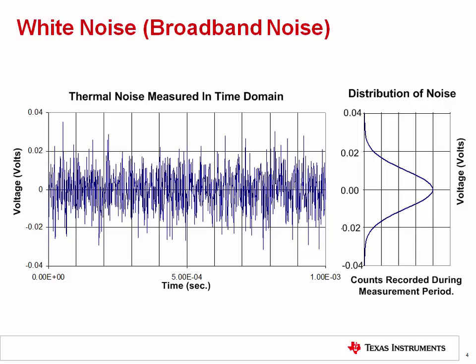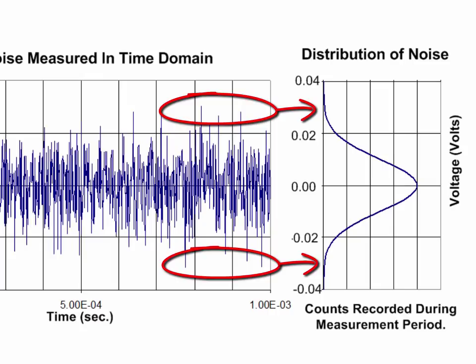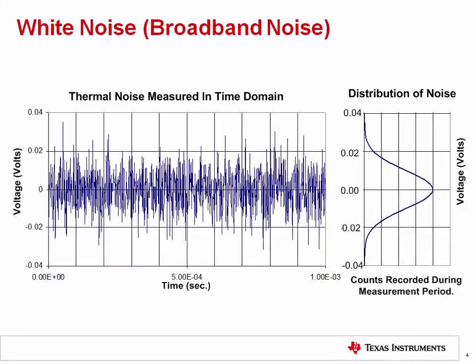In the next slide, we'll consider lower frequency noise sources. Also note the statistical distribution to the right hand of the slide. The distribution is Gaussian with a mean value of 0 volts and the skirts of the distribution at approximately plus or minus 40 millivolts. The distribution indicates that the probability of measuring noise near 0 volts is high, whereas the probability of measuring noise near the skirts of the distribution is relatively low. Later we will see how the distribution can be used to estimate the peak-to-peak value of the noise signal.